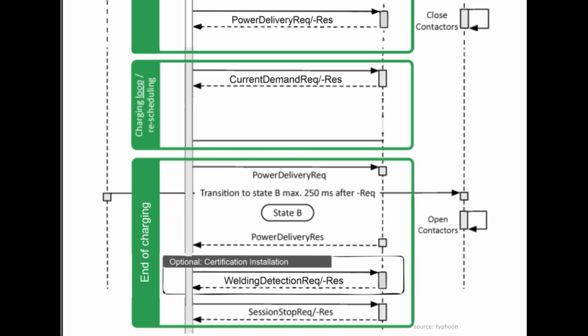1. Power down. The EVSE gradually reduces the current to avoid abrupt power interruptions. 2. Welding detection request response. A critical safety check occurs here. The system verifies that the contactors are not welded shut, ensuring they can safely open.